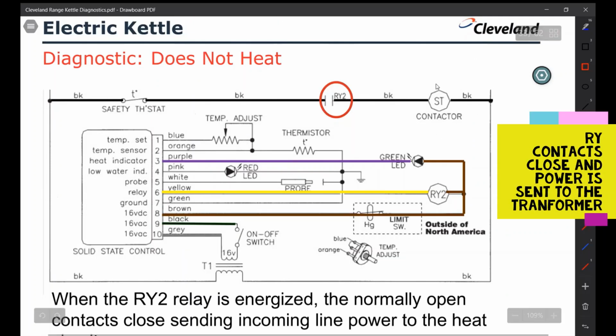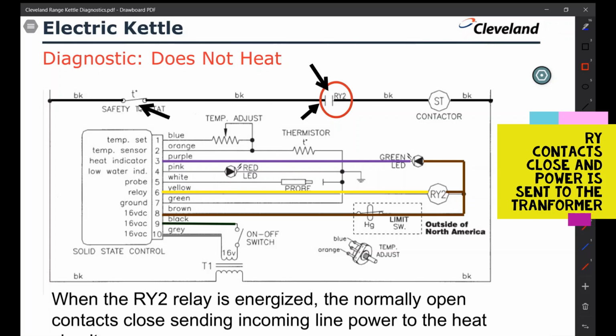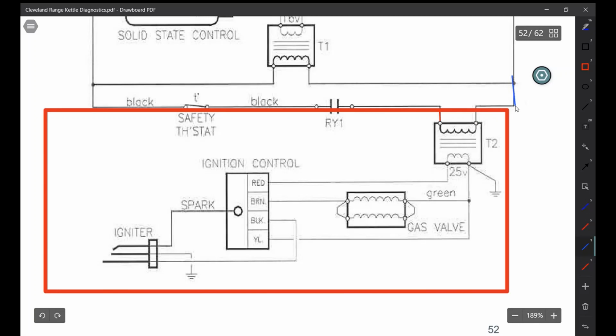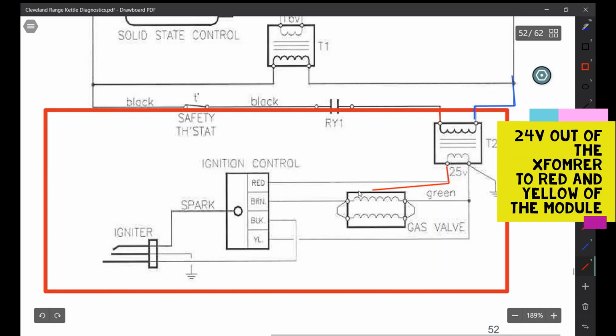Once our RY coil gets power, our RY contacts should close. If there's no power at the contacts here, obviously work backwards. Check to see if this high limit's open. If these contacts close, we get 120 volts to the transformer and it steps it down to 24 volts. We will get 120 volts to the transformer. The module now will get 24 volts across red and yellow.